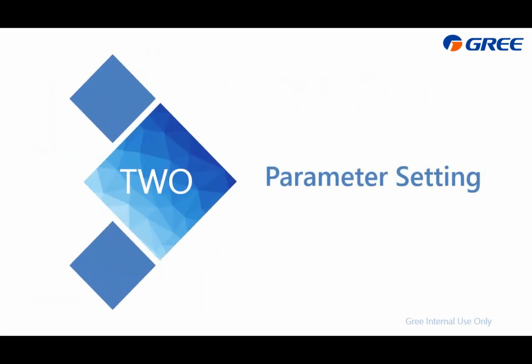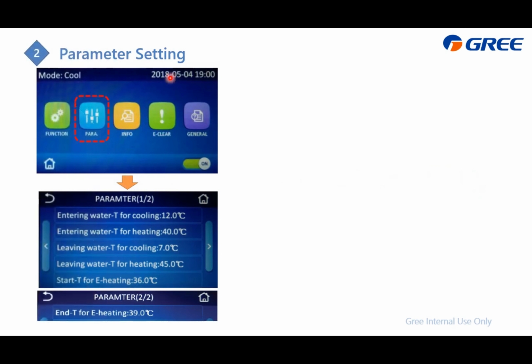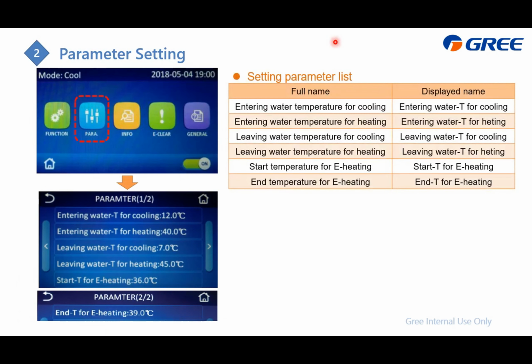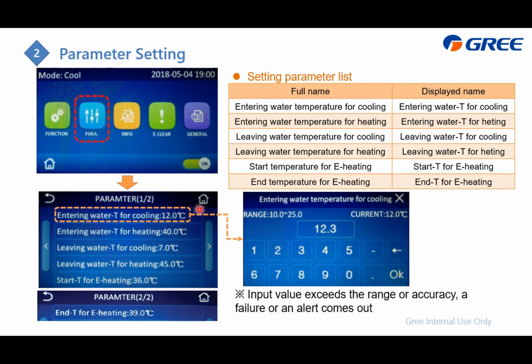Parameter setting. When you press this parameter, we go to this page, including two pages, which is this table. This table is the setting target of the cooling and heating, and this cooling and heating is the water in and out, depending on your control target in the function setting, which one you would like to select. And also you can set the heater on and off temperature. For example, if you would like to change this one, just press here, and then at this page it will display the allowable range, and also the current value.